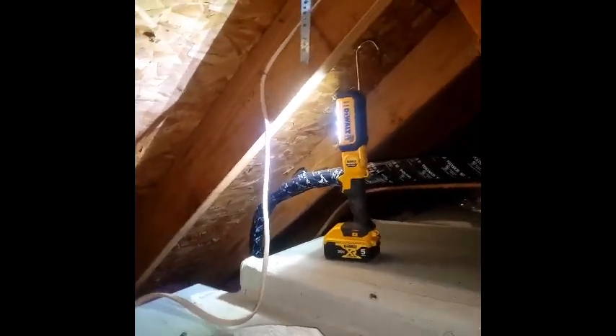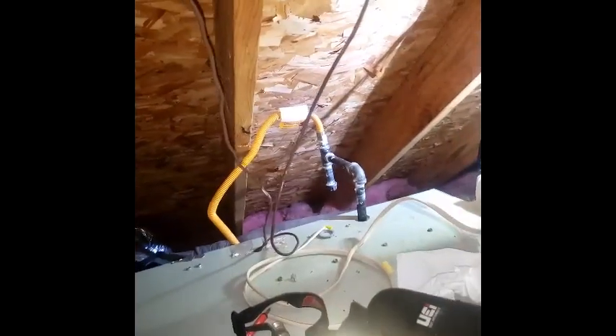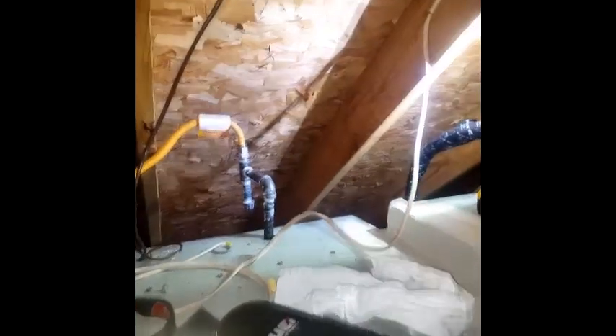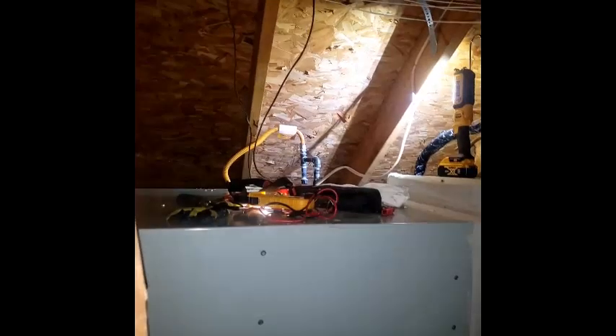They haven't really been bothering me, but if it starts heating up, this unit's fan needs a new control board, because the fan keeps running without 24 volts to it.